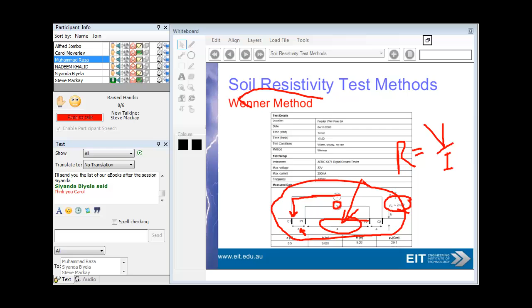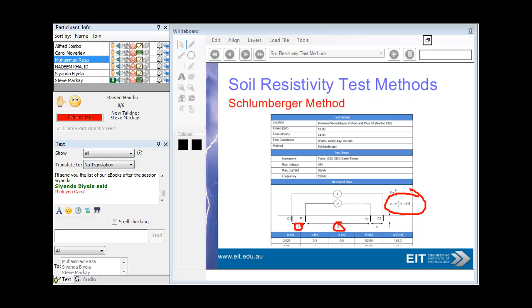The other method is the Schlumberger method, which is a little simpler. The distance between electrodes A is the same as A, though the diagram isn't to scale. This makes the calculation easier: resistivity equals 2 pi r, so it's very easy to calculate soil resistivity as 2 pi times the resistance measured from the voltage drop over the current. The other case has a variable distance, used when you can't set up your probes easily — that's the Schlumberger method. Again, very easy to measure soil resistivity this way.